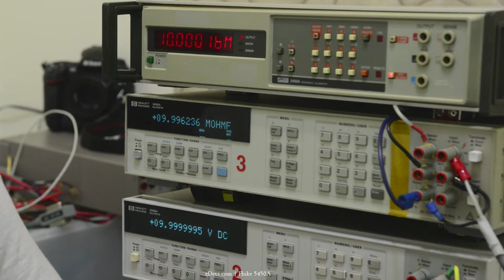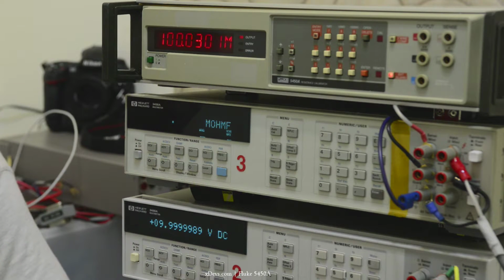So, 10,000,016 max, and measured is 9,996,236, which is a rough value, on the highest range, 100 megohm. Also, 4-wire connection for these high values is pointless, because the current is so small that any voltage change would be too small for the meter to distinguish from plain conversion noise.